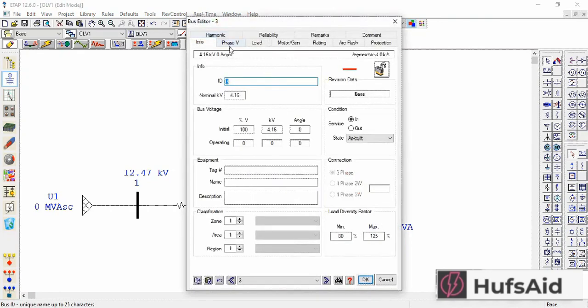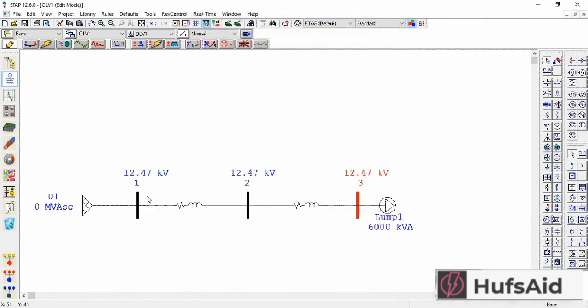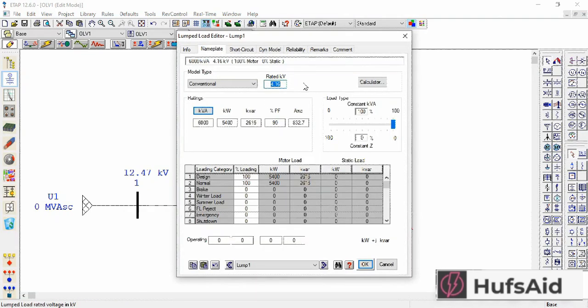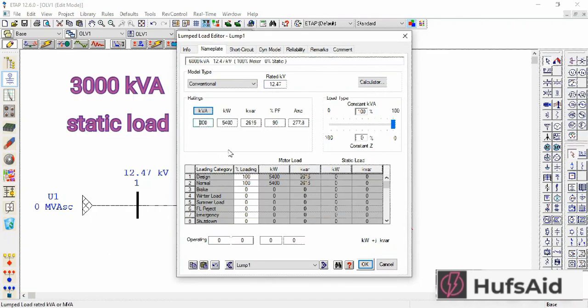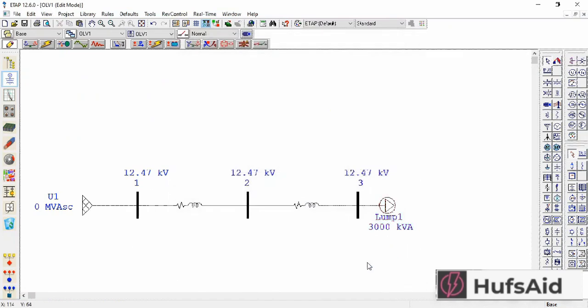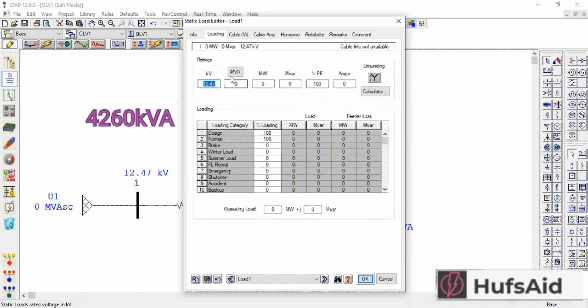Now that the transformer is removed, we are going to make the system voltage uniform. Let's change the system voltage — 4.16 kV should be changed to 12.47 kV — and also of the lump load. I am also changing the kVA, and I'm changing this load to a static load. I'm also going to connect another static load to Bus 2, which will be 4260 kVA.